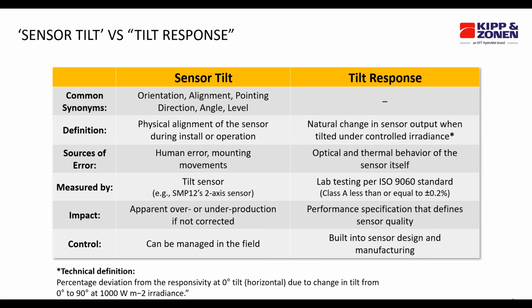When we talk about tilt response, we're talking about how the sensor physically responds to changes in sensor alignment and the allowable variance that we as manufacturers need to design for per the standards when we pick detectors, material qualities, and control assembly quality. The Class A specification limit for tilt response is only 0.2%, and it's our job as manufacturers to take care of minimizing this error of tilt response.